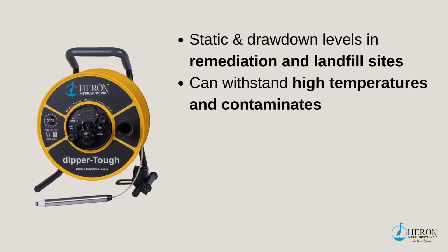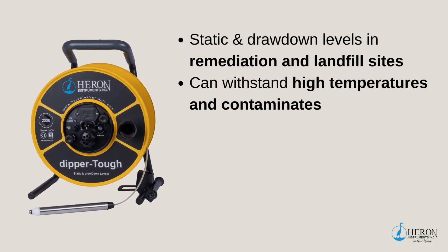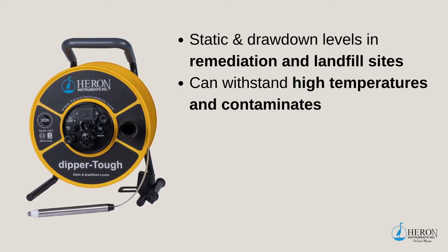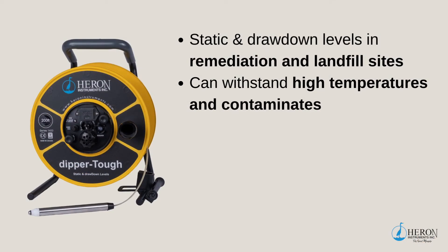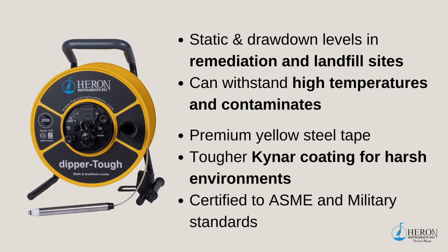The Dipper-Tough was designed for clients that need a tougher water level meter. This unit is ideal for measuring static and drawdown levels in remediation and landfill sites, where higher temperatures and contaminants can be an issue. The premium yellow steel tape has a tougher Kynar coating to protect the markings in harsher environments, providing a longer tape life than standard tape units. This tape is certified to ASME and military standards.